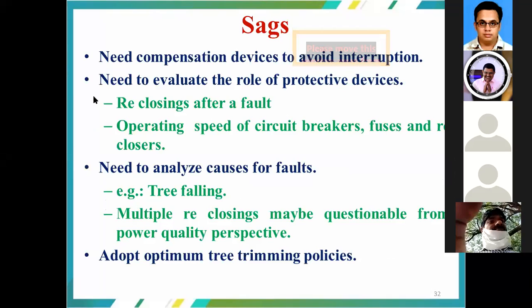And sags need compensation devices to avoid the interruption. We need to evaluate the role of protective devices, that is reclosings after a fault, the operating speed of circuit breakers, fuses and reclosers, and analyze the cause for faults, that is a tree falling, or multiple reclosing may be questionable from a power quality perspective, and adopt optimum policies.